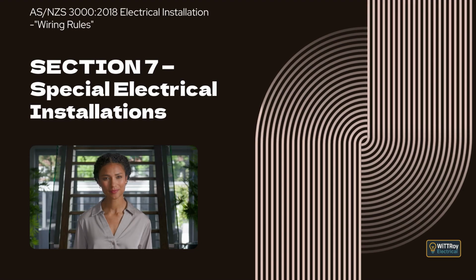The notes explain that other standards give guidance for emergency power in hospitals, clarify how the term safety services has been used in different editions and building codes, and explain that fire resistance level is expressed in minutes and relates to structural adequacy, integrity, and insulation as defined by the relevant building and fire standards. Clause 7.2.2 Supply Systems. This clause explains how power supplies for safety services must be arranged.